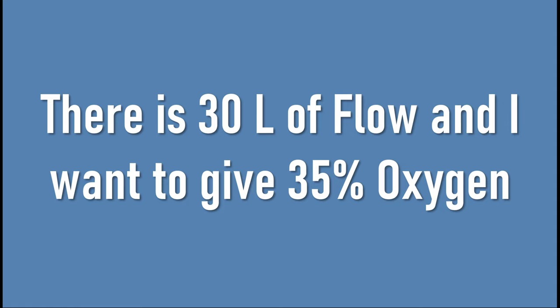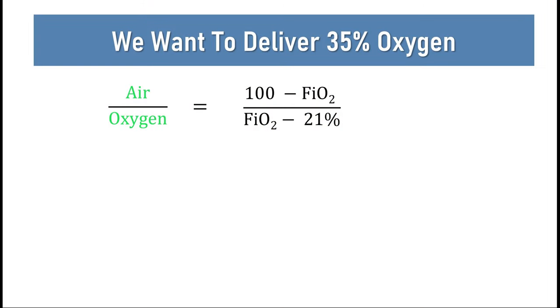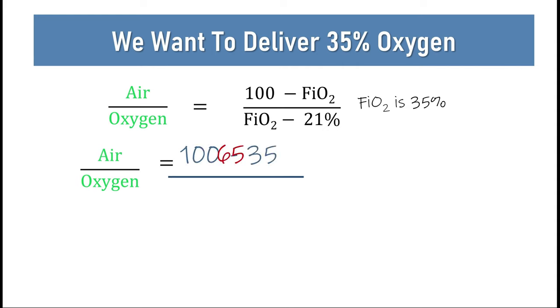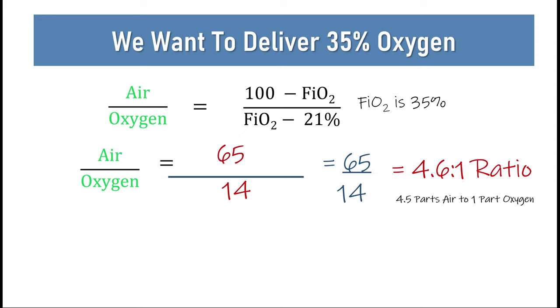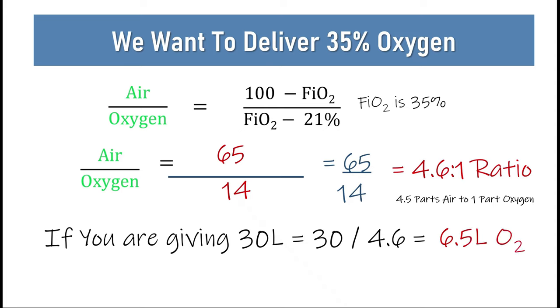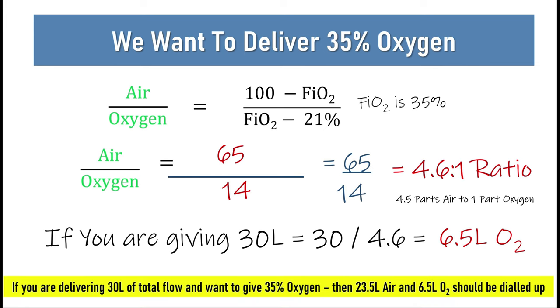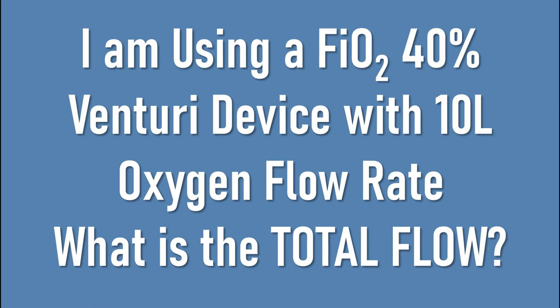Another scenario: 30 litres of flow and I want to give 35% oxygen — how many litres of oxygen do I need? Feeding 35% into the equation: (100 − 35) ÷ (35 − 21) = 65 ÷ 14 ≈ 4.6 to 1 ratio — about 4.5 parts air to one part oxygen. With 30 litres total flow: 30 ÷ 4.6 ≈ 6.5 litres of oxygen. So you need 23.5 litres of air and 6.5 litres of oxygen to deliver 35% oxygen at 30 litres of flow.